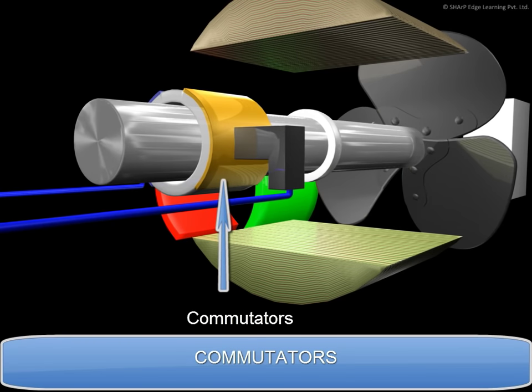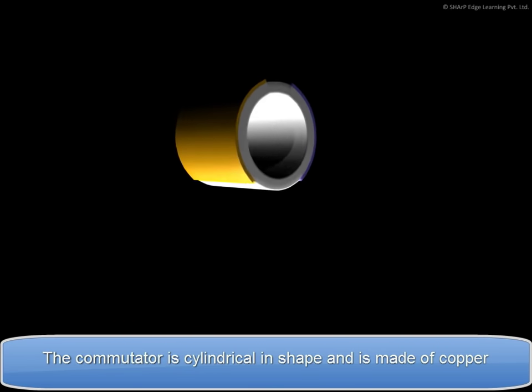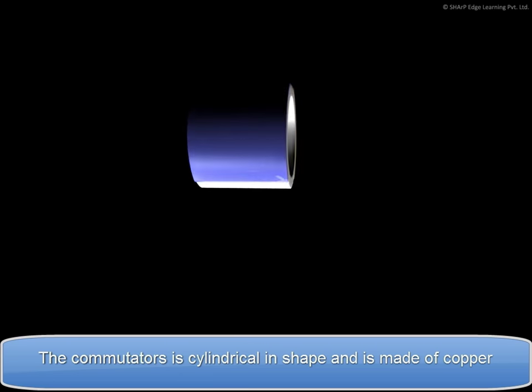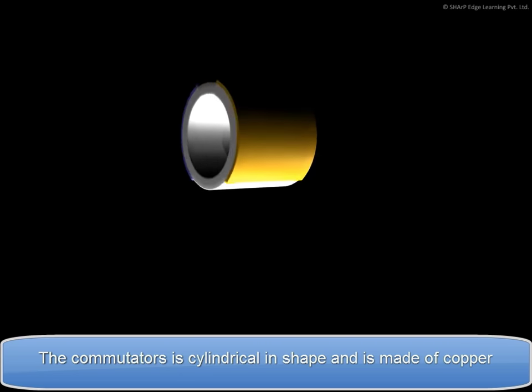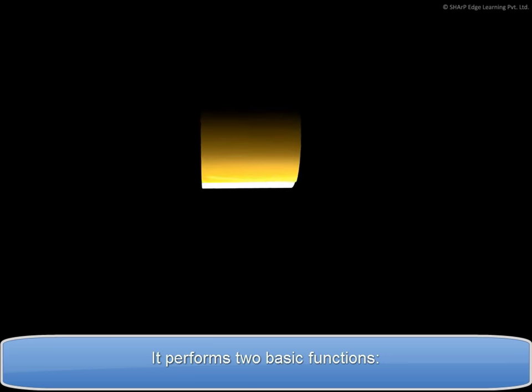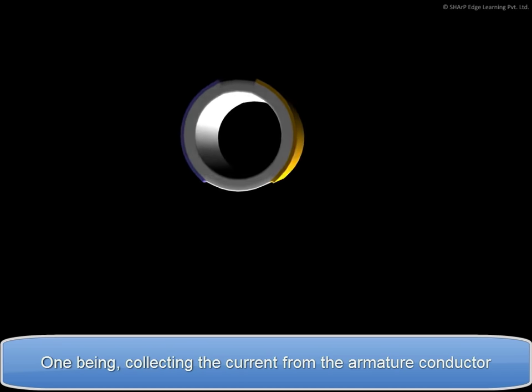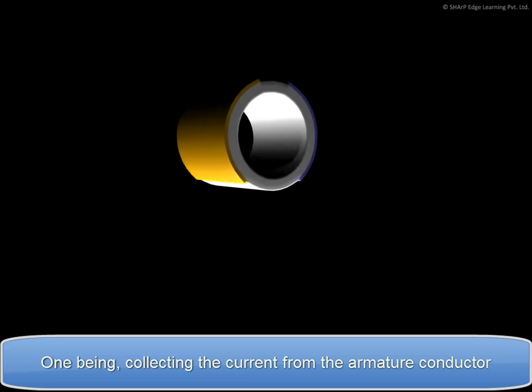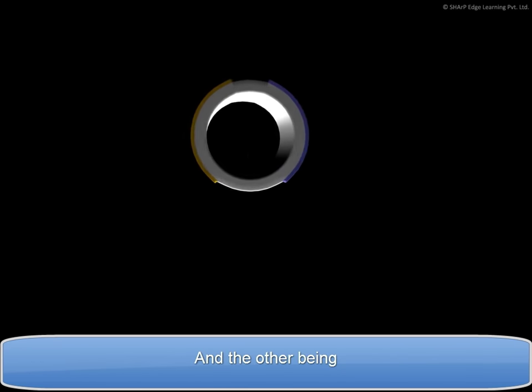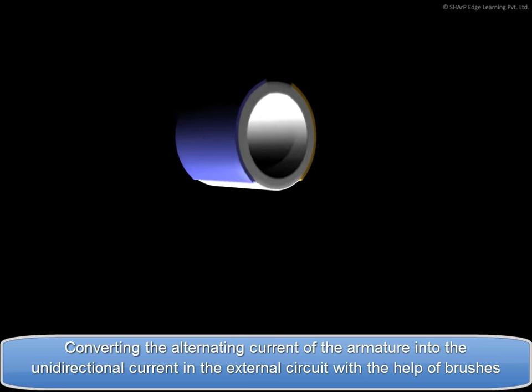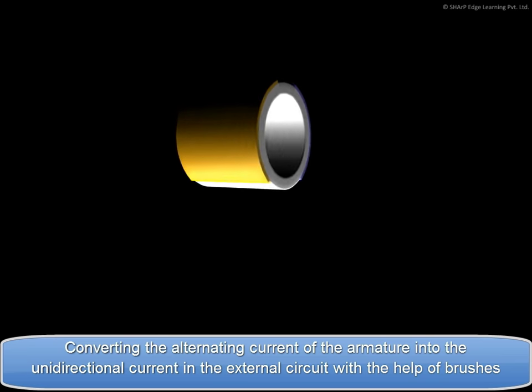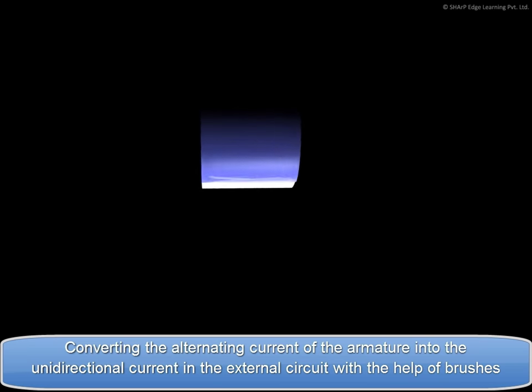Commutator. The commutator is cylindrical in shape and is made up of copper. It performs two basic functions. One being collecting the current from the armature conductor. And the other being converting the alternating current of the armature into the unidirectional current in the external circuit with the help of brushes.